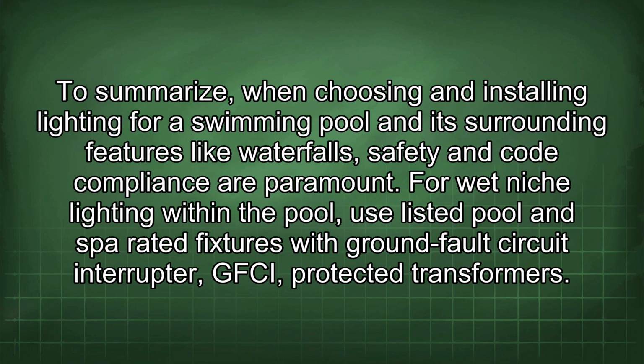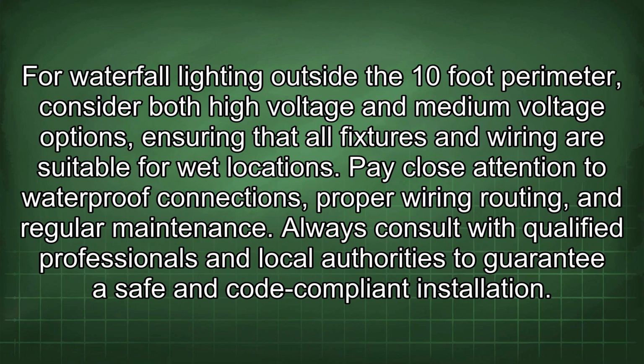To summarize, when choosing and installing lighting for a swimming pool and its surrounding features like waterfalls, safety and code compliance are paramount. For wet niche lighting within the pool, use listed pool and spa rated fixtures with ground fault circuit interrupter, GFCI, protected transformers. For waterfall lighting outside the 10-foot perimeter, consider both high voltage and medium voltage options, ensuring that all fixtures and wiring are suitable for wet locations. Pay close attention to waterproof connections, proper wiring routing, and regular maintenance. Always consult with qualified professionals and local authorities to guarantee a safe and code-compliant installation.